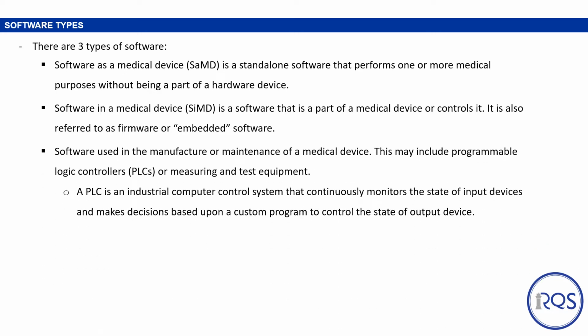And lastly, we have software that is used in manufacturing or maintenance of a medical device, and this is pretty self-explanatory. This includes programmable logic controllers, or PLCs, or measuring and test equipment. A PLC is an industrial computer control system that continuously monitors the state of input devices and makes decisions based upon a custom program to control the state of the output device.